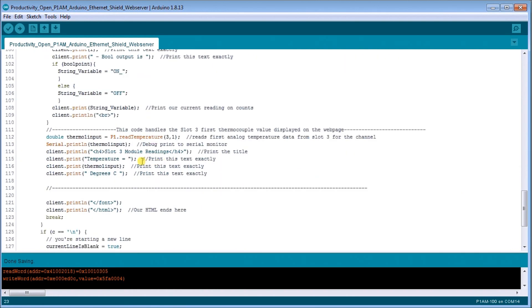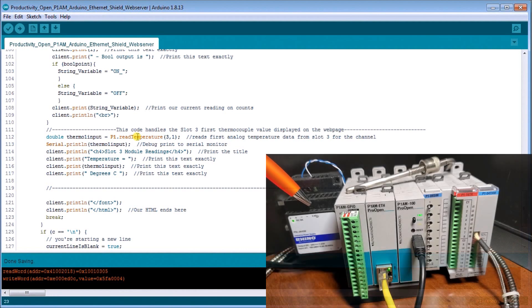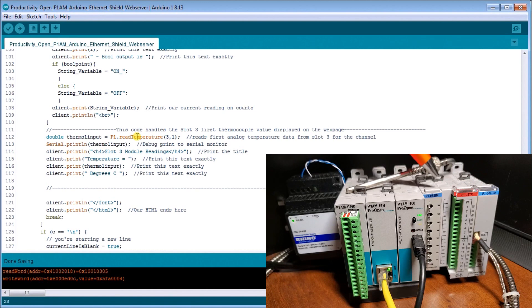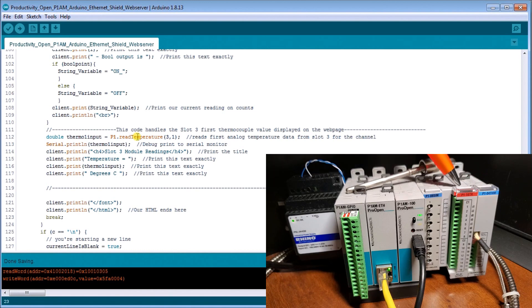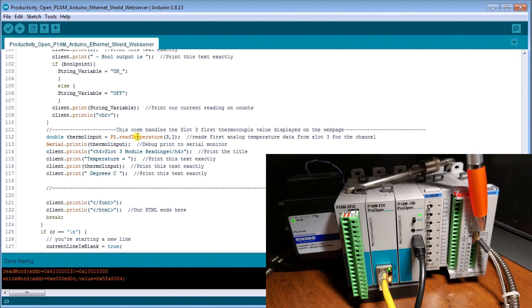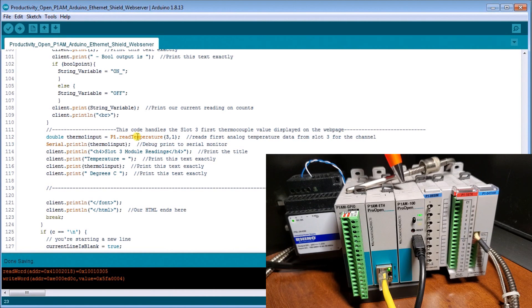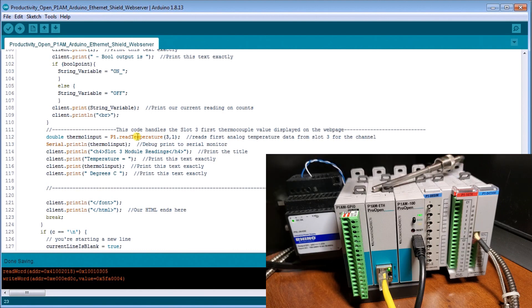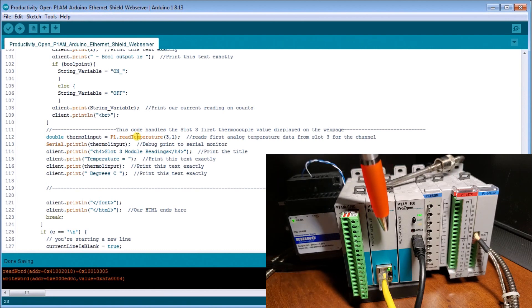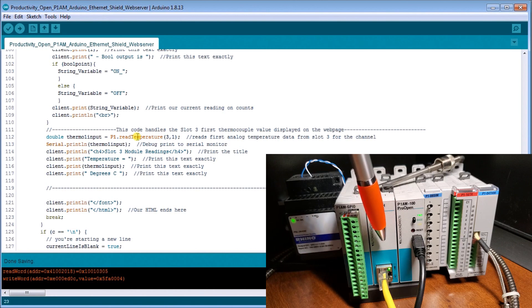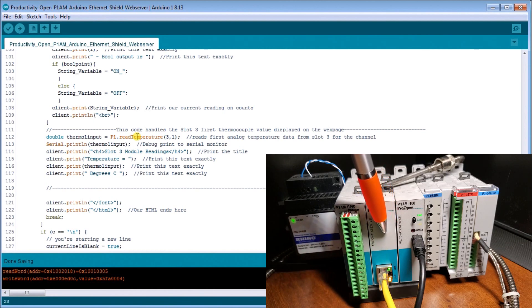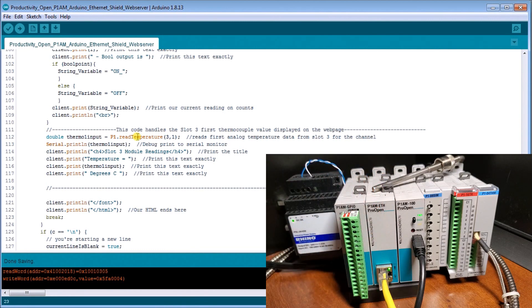And now what we can do is we can look at our hardware that we have. And you'll see here, we have our Rhino powering up our cards and that's our expansion cards right here, which we have our simulator input. We have our discrete outputs, which are relays. And then we have our thermocouple card right here. And we're using the first input using a J type thermocouple back into this unit right here. So this is our end of our thermocouple unit itself. Then we're connecting to our ethernet module right here. Remember that the sticker for the MAC address is actually on the side of this. So it's important to write that down before you actually assemble this whole structure. And you see, this is our ethernet cable going back to our network and we are in run mode here.